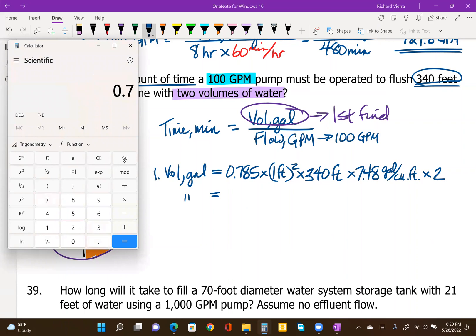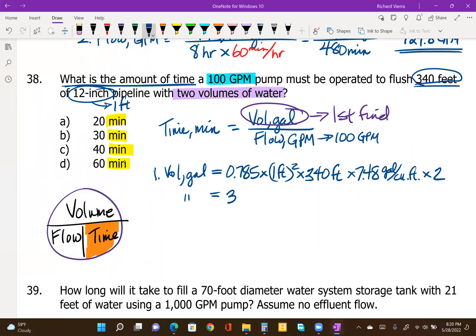So 0.785 times one foot squared, doesn't change anything, times 340 and times 7.48 to flush it through one time. It would take a little under 2,000 gallons. We're doing it twice. So I'm multiplying that times 2. So it looks like 3,993 gallons total to flush it through twice.